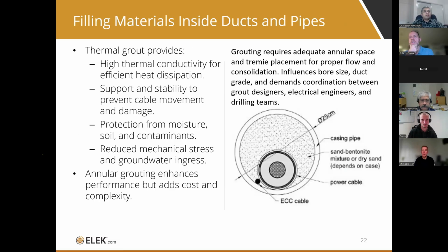Filling materials inside ducts and pipes: it is very common to install filling materials inside HDDs. It's multi-purpose. So the thermal grout provides high thermal conductivity, of course, for efficient heat transfer. Air is a poor thermal conductor. It's more of an insulator. These grouts have good thermal properties, that's what they're designed to do.